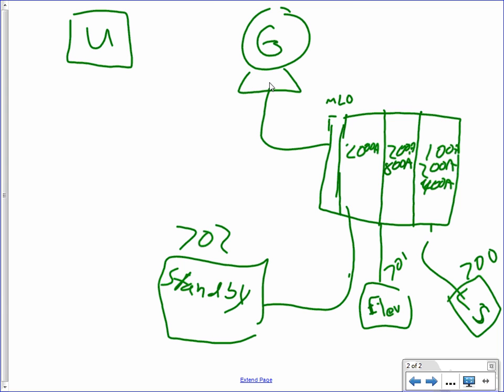Do they put a main in the gen then? Put a main in the gen. Yeah, put them in again. Yep. Or use the six disconnect rule, like I'm doing right now. Or for your job, since it's really just two, they may just put two right at the gen: a 2,000 amp breaker and a 100 amp breaker in separate enclosures beside each other and feed. But I'm just giving this as a what-if example.